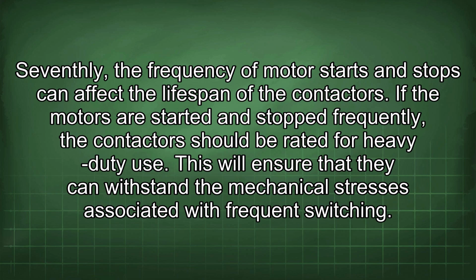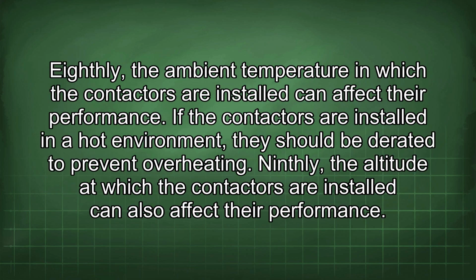Seventhly, the frequency of motor starts and stops can affect the lifespan of the contactors. If the motors are started and stopped frequently, the contactors should be rated for heavy-duty use. This will ensure that they can withstand the mechanical stresses associated with frequent switching. Eighthly, the ambient temperature in which the contactors are installed can affect their performance. If the contactors are installed in a hot environment, they should be derated to prevent overheating.